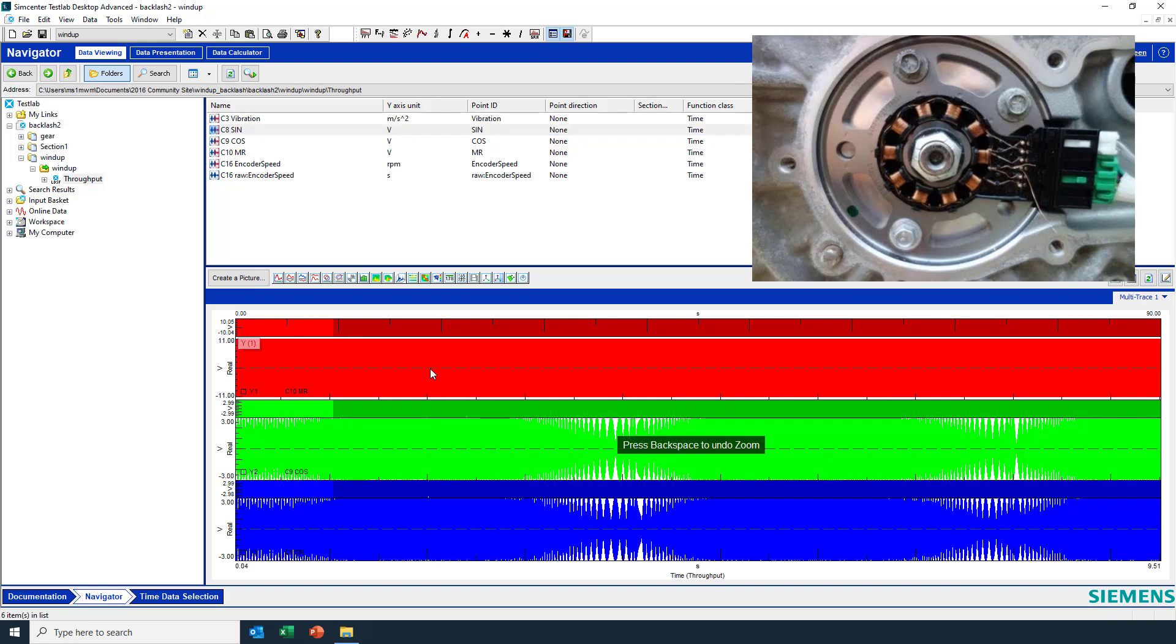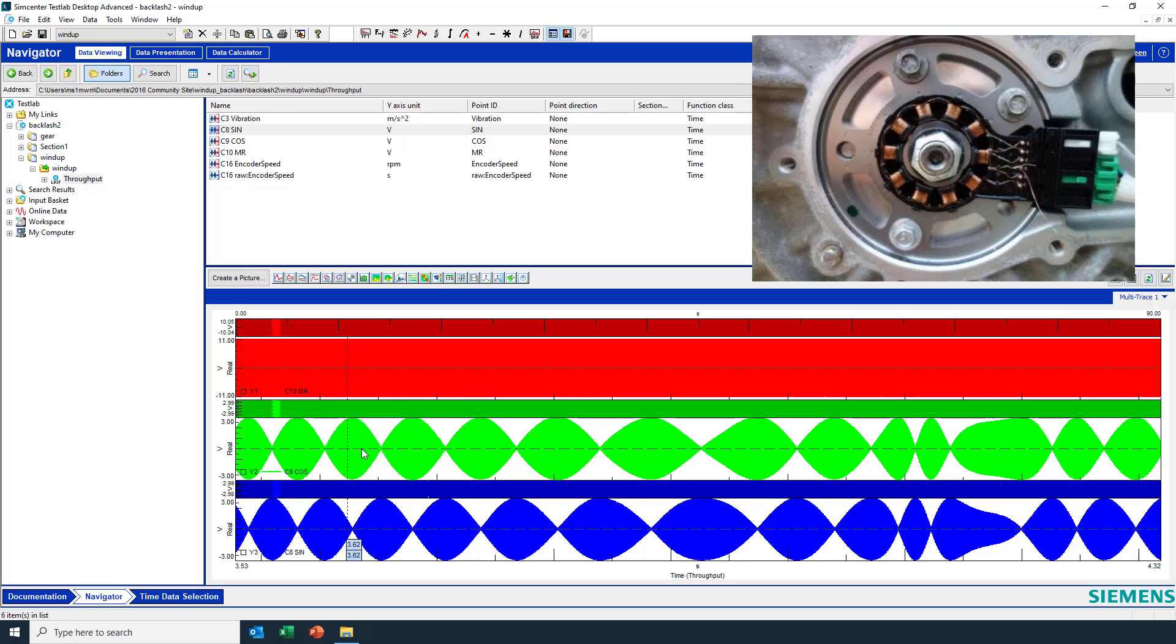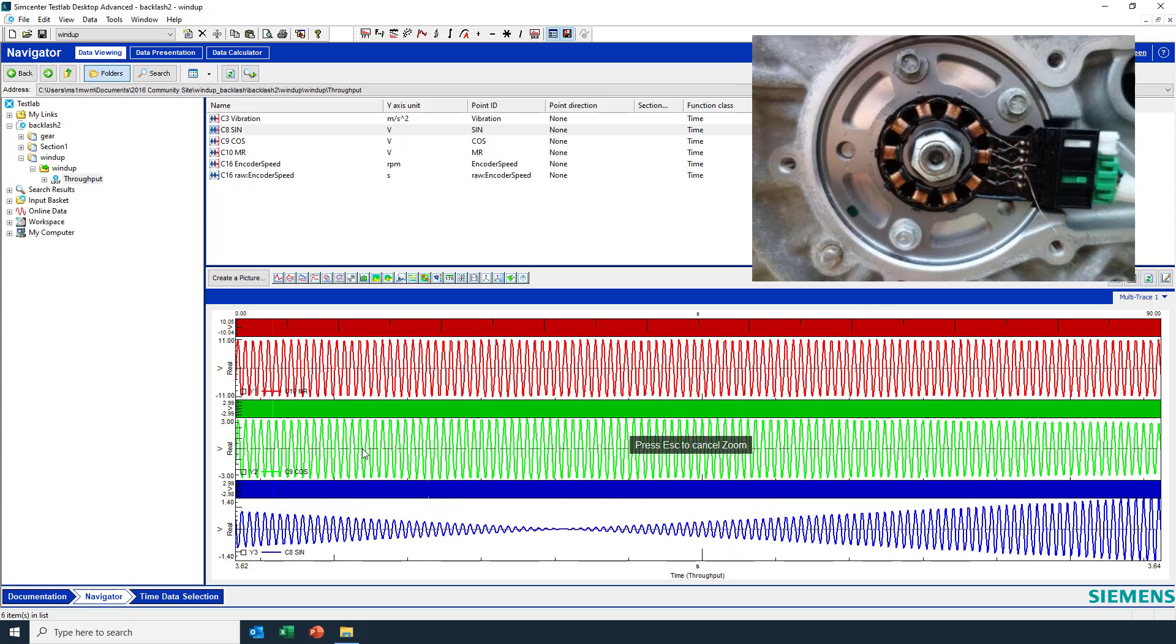If I was to zoom out a little bit you can see that the cosine and sine wave do lag each other by 90 degrees as expected. If we zoom in enough you can also see that the sine and cosine wave are the same voltage, same frequency as the excitation, but the amplitude is modulated according to the rotational position in the resolver.